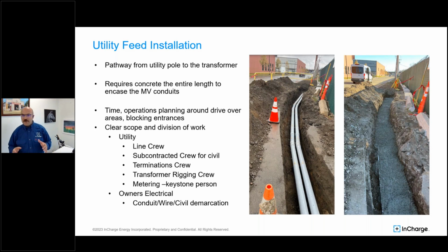This part gets fuzzy in some jurisdictions. You have to make sure it's clear who's handling what part of it, because you have the physical path of conduit from the pole or from the big green utility box somewhere out along the street. You have that medium voltage conduit and wiring that has to get from there to wherever your transformer is going to go, and that's usually a much deeper trench than what you might have out on your lot. Also the conduits have to be backfilled with concrete -- they've got a slurry. There's more actions that have to happen here.